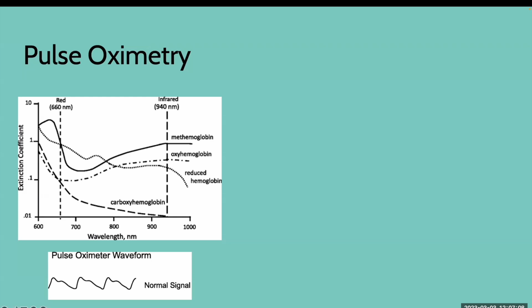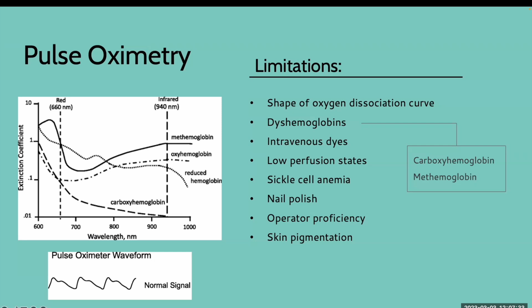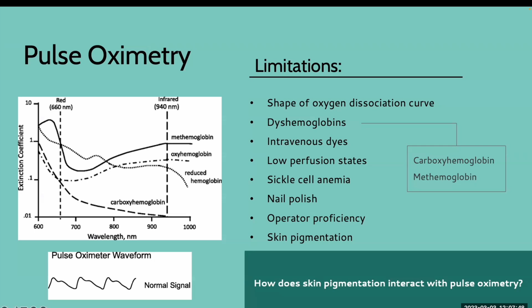One example is low perfusion states, which include low cardiac output, vasoconstriction, and hypothermia. Operator proficiency is also often overlooked and represents a critical layer of communication between the device and the provider. So SpO2 values are often reported and documented without adequately assessing these limitations. Today, I want to take a closer look at skin pigmentation. Deoxyhemoglobin and melanin are the primary light absorbers at these wavelengths. And so measurements of light will vary with skin pigmentation depending on tissue perfusion, probe location, shape, and color.